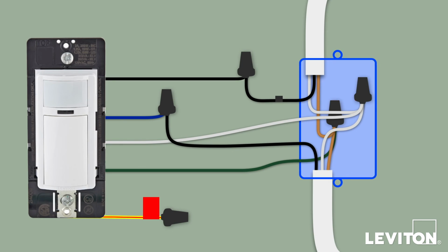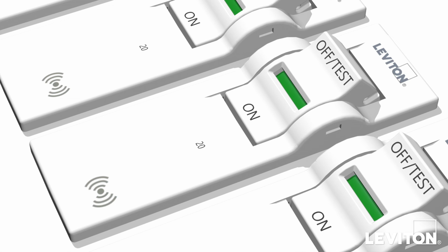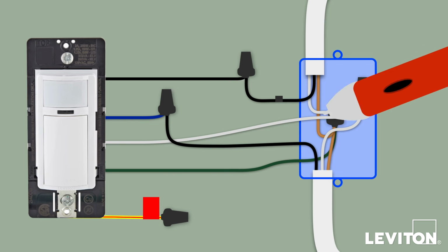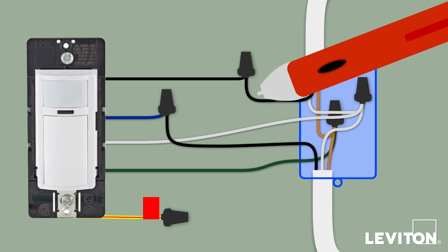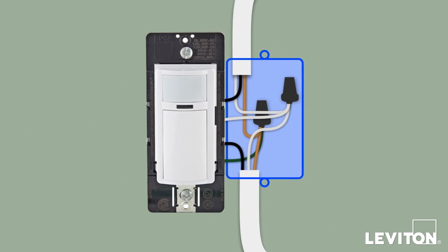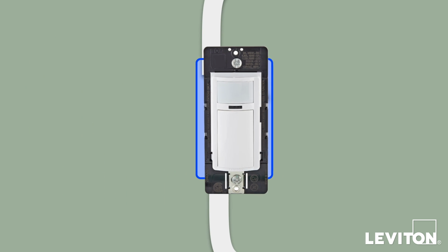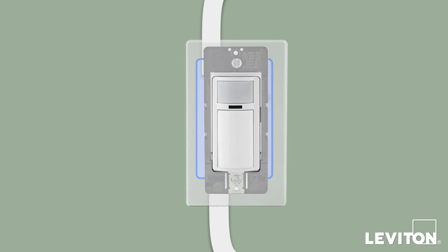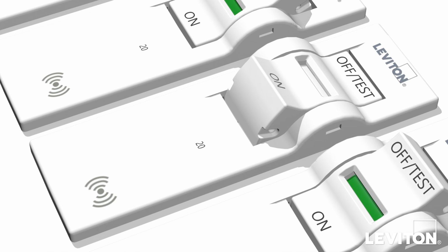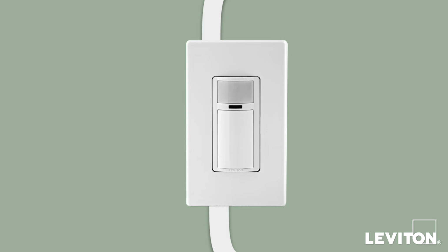Now we'll mount the device to complete the installation. Turn off power at the circuit breaker and test to ensure the power is off. Gently bend the wires and push them into the wall box. Screw the sensor into the wall box. Install the wall plate. Restore power at the circuit breaker. Your Leviton Decora Occupancy or Vacancy sensor is now ready for use.